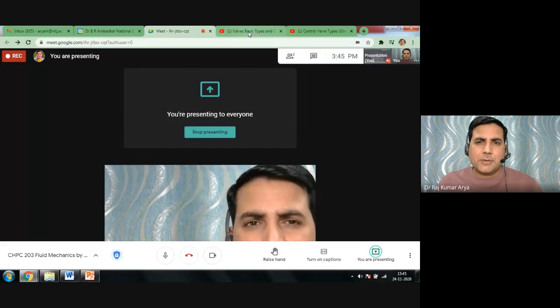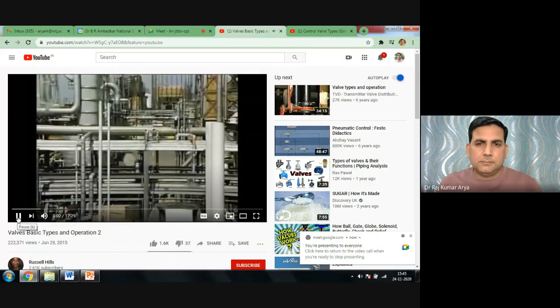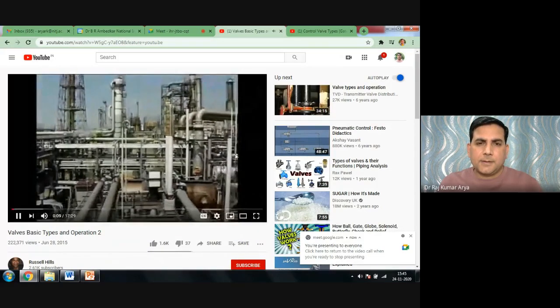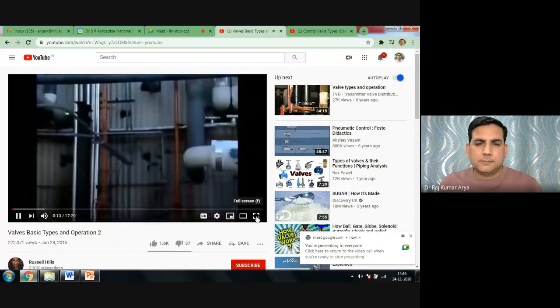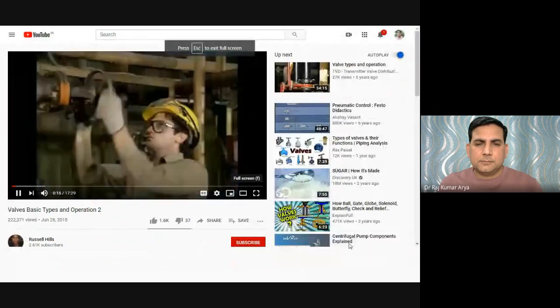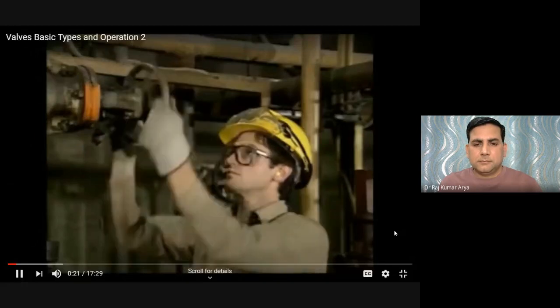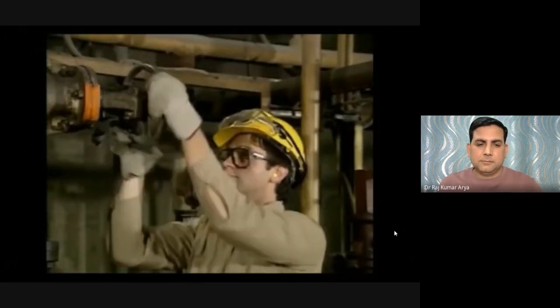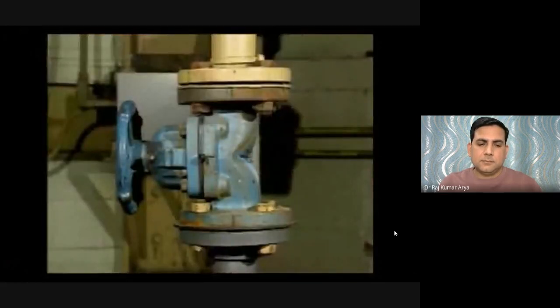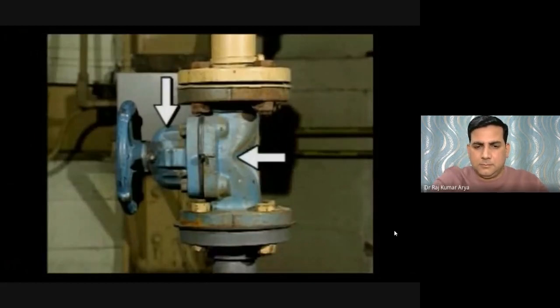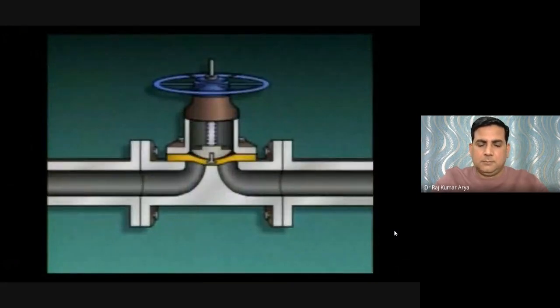Most industrial facilities and process systems handle many different types of fluids. These fluids are moved from one location to another by piping systems, and their flow is controlled by valves. A diaphragm valve is easy to recognize by its bell-shaped bonnet. A flexible diaphragm is positioned on or near a weir or dam-shaped seat to control or stop fluid flow. A stud connects the diaphragm to a plunger.